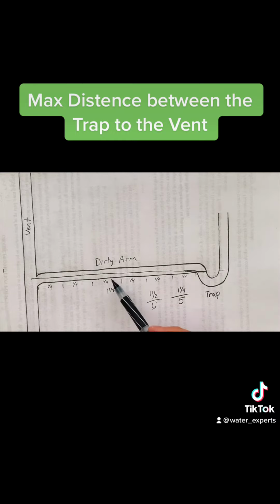Now, this pipe is 1.5 inches. So that means that the maximum distance from the vent to the trap can be 6 feet, because if it is flowing at a 1/4 inch per foot, it breaches the maximum height of the pipe itself. And once we get above that point of 1.5 inches, which is the pipe size, we're now getting rid of this air gap over here. And the air can no longer flow into the dirty arm, and this will eventually be siphoned out. So that is why there is a maximum distance.